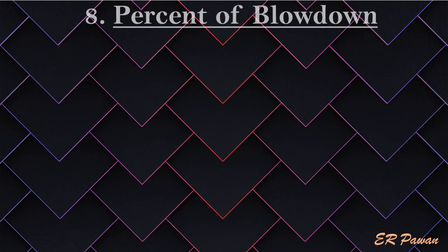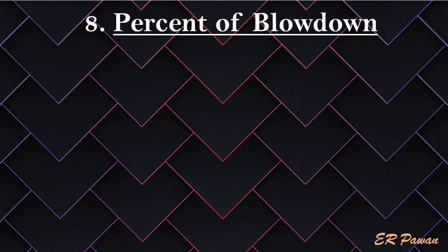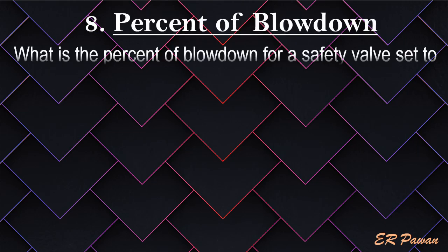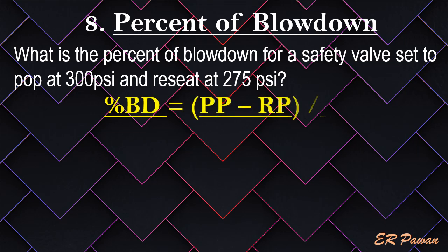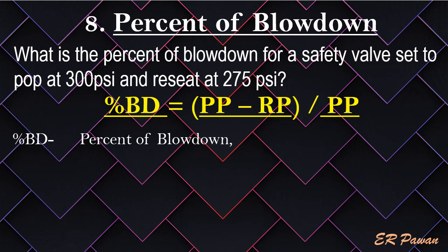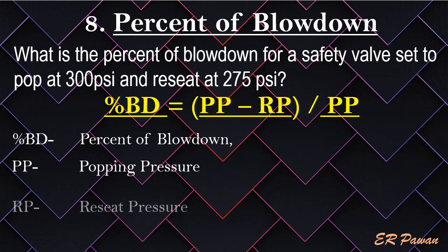Formula 8 — Percent of Blowdown. What is the percent of blowdown for a safety valve set to pop at 300 pounds per square inch and reseat at 275 pounds per square inch? Percent of blowdown equals popping pressure minus reseat pressure divided by popping pressure. Where PP = popping pressure, RP = reseat pressure. Let's put the value in the formula.